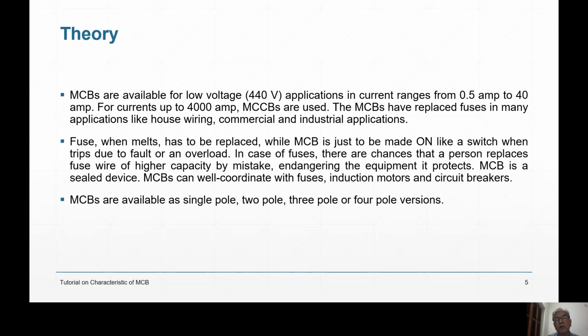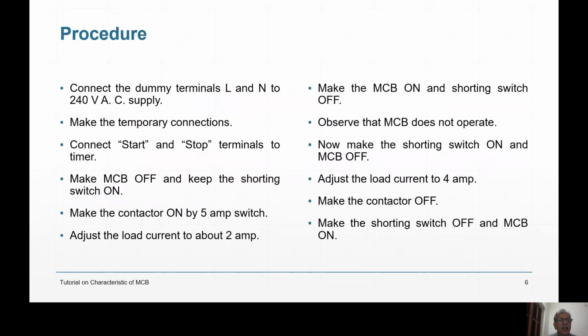In MCB, this is not possible. In MCB, this is not possible because it is a sealed device. So it operates exactly according to its characteristic. MCBs are available in single pole version, 2-pole version, 3-pole version, and 4-pole version. All versions are available.